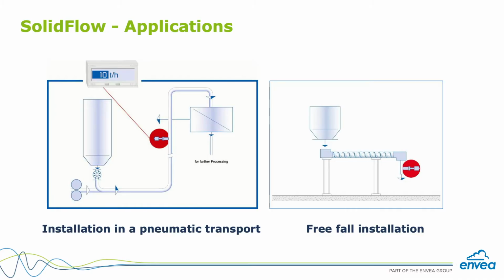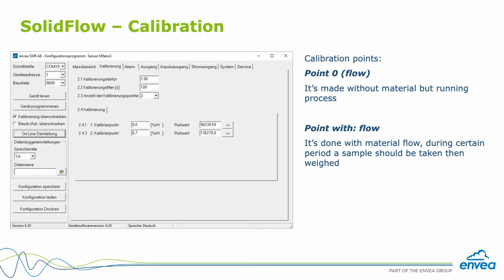Sounds good. So in a free fall application, probably pretty easy to calibrate, but with pneumatic conveying, is calibration a challenge? For the calibration, the customer has to know the mass flow amount. They should weigh the sample before or after the sensor, and once we start conveying, the sensor will log this data. We should know the mass flow for that point.